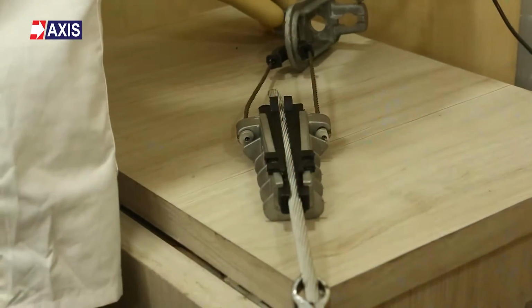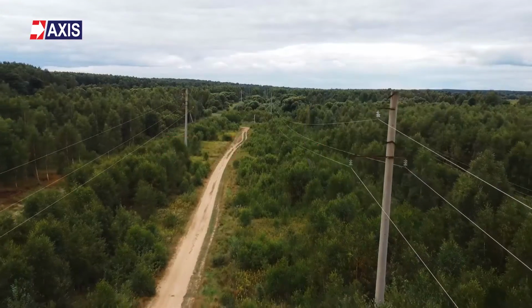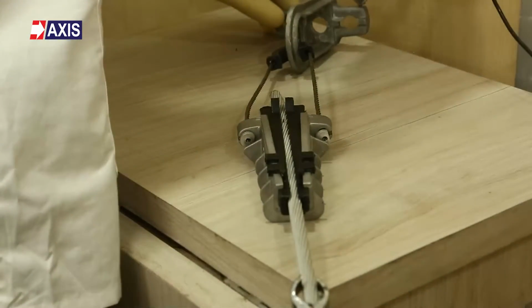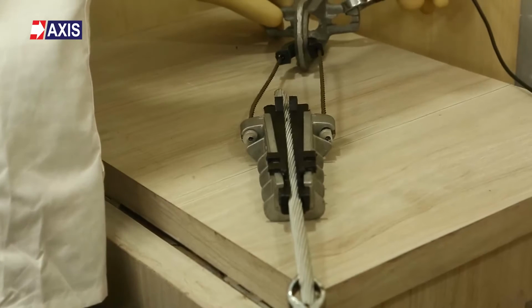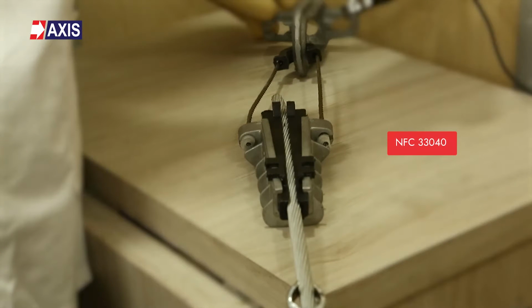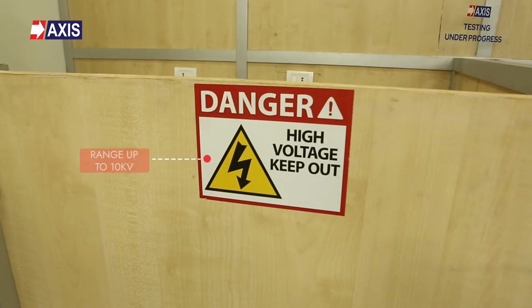In this video, we perform the test on an anchoring clamp which is used on distribution lines to tension the cables. These clamps need to comply with the high voltage test requirements as per the NFC 33040 standard, which requires a 6 kV test for 60 seconds. Note, the high voltage tester has a range of up to 10 kV.